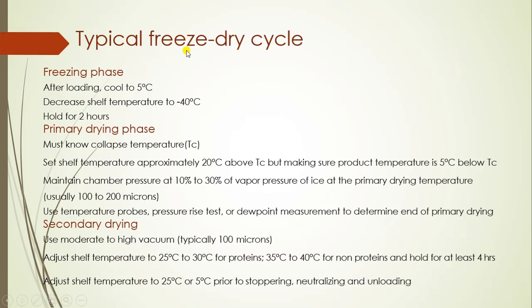This is the hierarchy of a typical freeze-dry cycle. First is the freezing phase: after loading, cooling is done to 5 degrees Celsius, then shelf temperature decreases to minus 40 degrees Celsius and is held generally for 2 hours for freezing of the solution. The next step is the primary drying phase, which should be performed below the collapse temperature. The shelf temperature must be approximately 20 degrees Celsius above the collapse temperature, but ensure that product temperature is 5 degrees Celsius below the critical collapse temperature. Chamber pressure is maintained at 10 to 30 percent of the vapor pressure of ice at the primary drying temperature, usually 100 to 200 microns Hg.